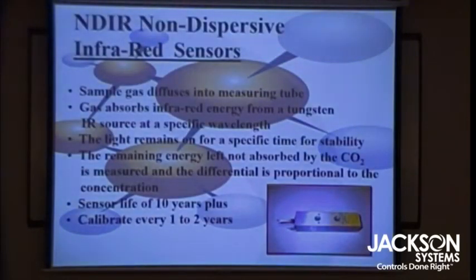The third type we have are infrared sensors, and this is a non-consumable sensor because you can have a very high concentration of gas and you're not going to wear out the sensor because there's no chemical interaction with the sensor element. And basically the way it works is that you have a light source at one end of an optical bench, and inside the bench, which is just a pathway, you have a very, very highly polished reflective surface. You choose the light source such that the wavelength is the same as the gas you're looking at. So if there's no gas present, 100% of the light is transmitted and it's collected by the other end of the source. If there is gas present that has the same wavelength as your light source, it's absorbed and you don't get 100% transmittance. So you actually see a decrease in the signal, and that is proportional to your gas concentration.